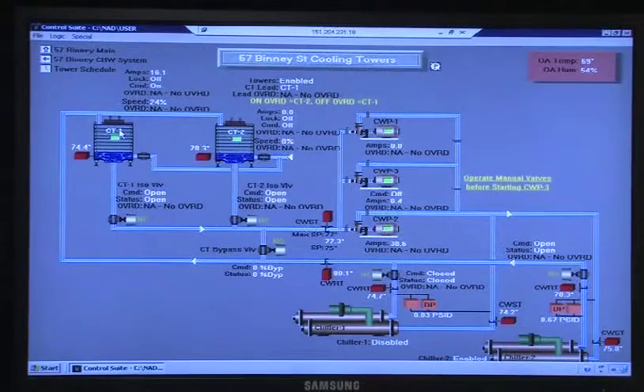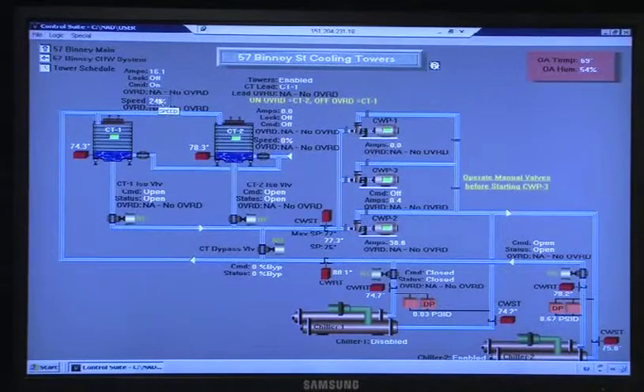If the water continues to rise, there's another safety in there as far as for like a lag. It will actually bring on another tower fan if it can't bring the temperature down in the water. I don't know if that number is reflected on the screen there, but there's an offset set point, like the 3 degree. So if it goes to 80 degrees, it will bring the second tower on, and the second tower will start if the first one fails for some reason, being the pumps, the VFD. There's nothing in the tower per se, but if the VFD fails, it will kick on the other one.